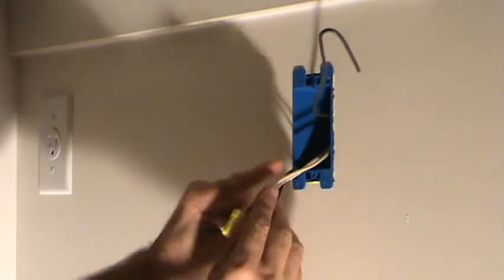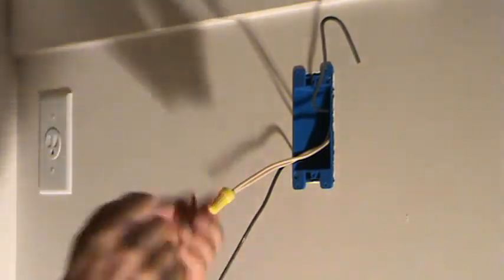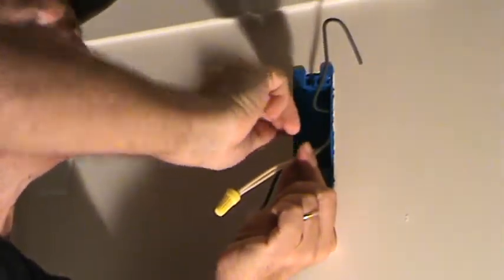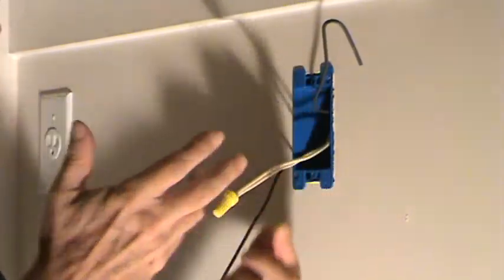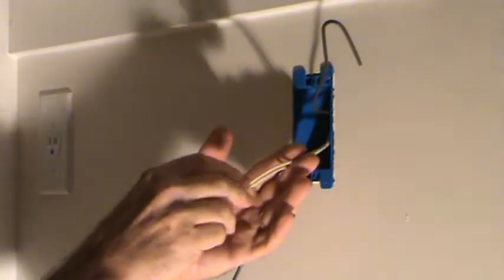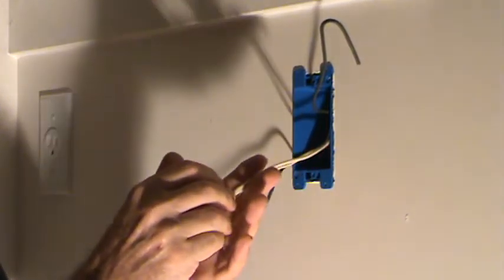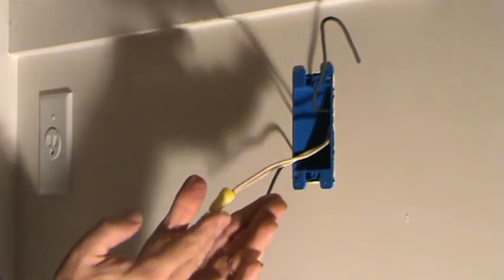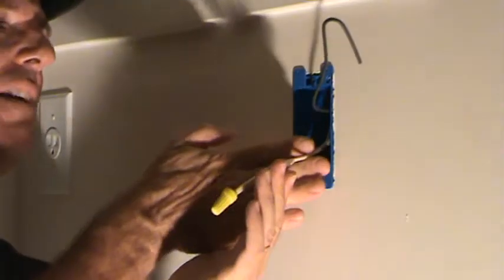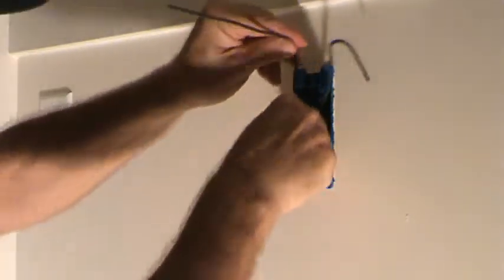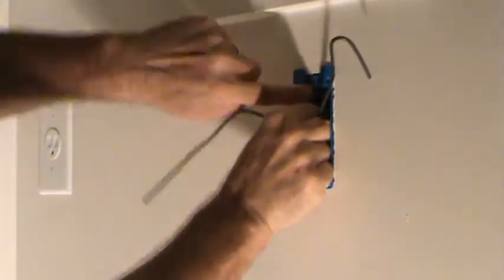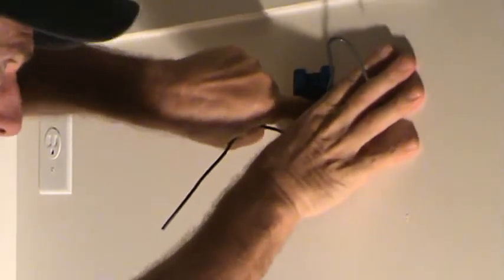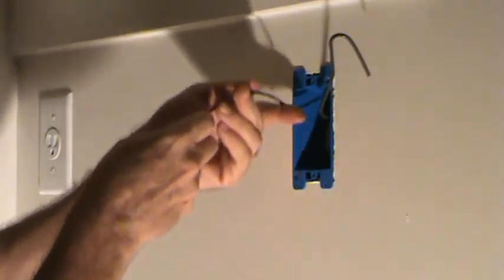But now this one here too, because I'm out this long, I'm going to wrap it twice. Now do you want to cut it real close with the wire nut there and then push that straight up? You could do that, but you want to be nice to the next electrician or somebody who's going to work on this box. You want to give yourself enough wire so that you don't have to feel like you're right up here tight with the work. Bend that halfway, push that in there, redirect my wires in here a little bit. Push that to the back of the wall, back of the box like that.